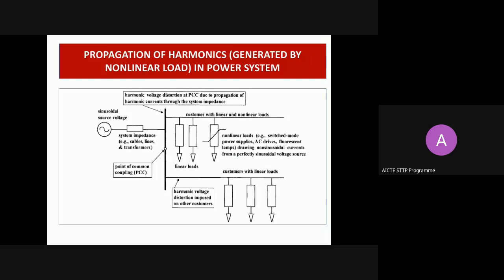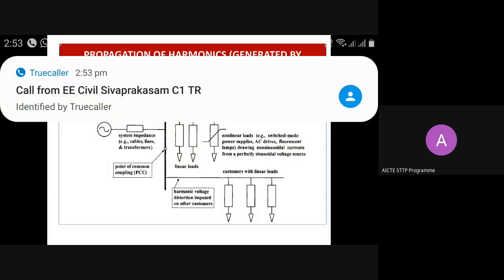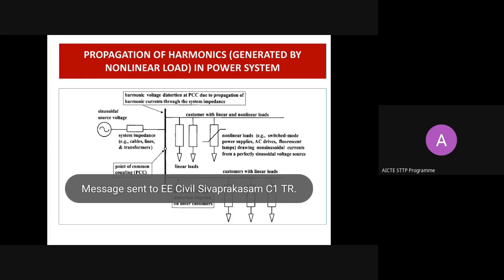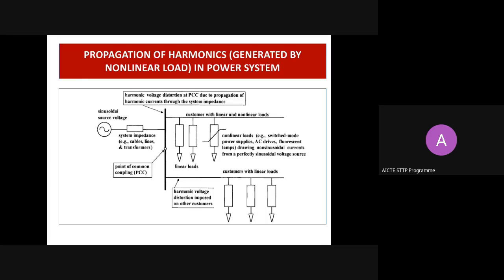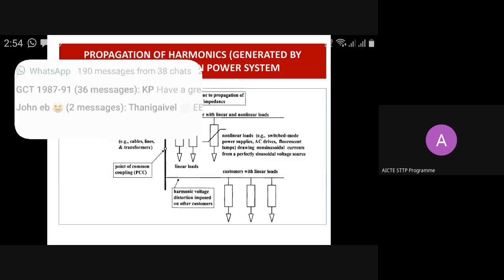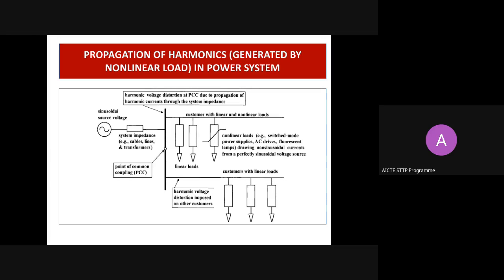Sinusoidal source voltage is quality power. We are providing quality power at the point of common coupling, where the loads are connected. Certain loads are linear loads, certain loads are non-linear loads. There is not much bother about linear loads. Customers with linear loads are not much disturbing the system, but customers with non-linear loads are drawing more harmonic current. This harmonic current has an impact on the voltage at the point of common coupling.